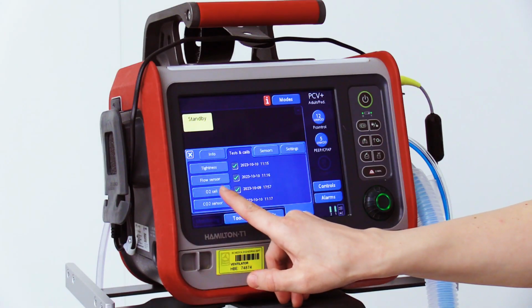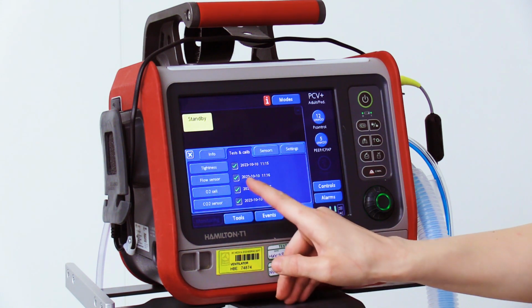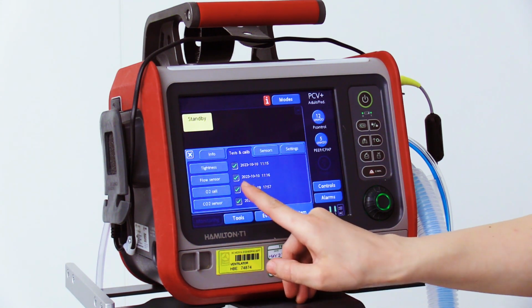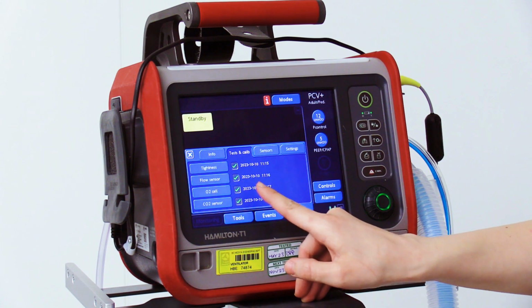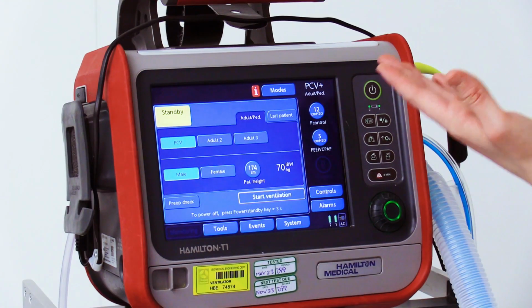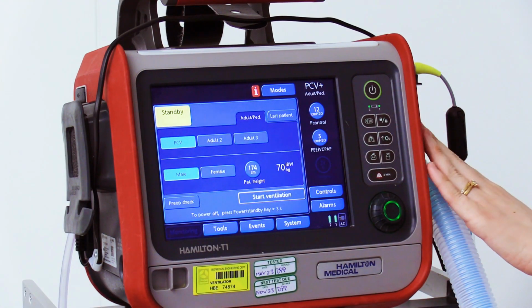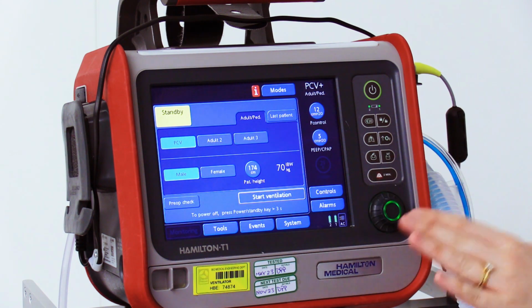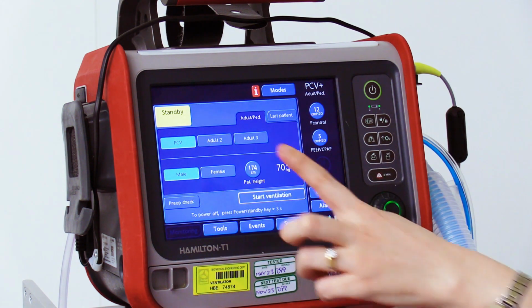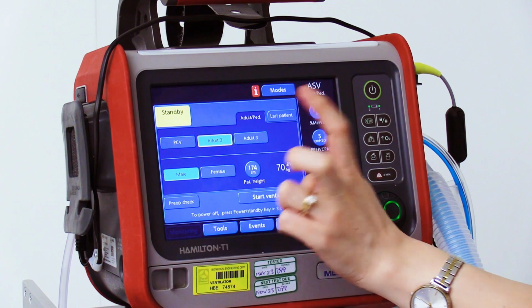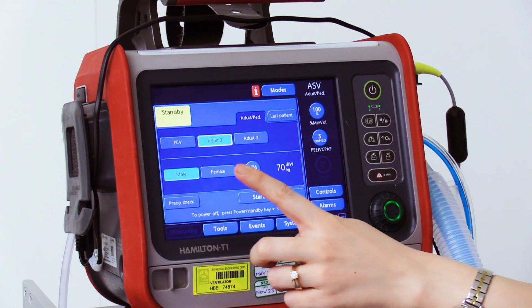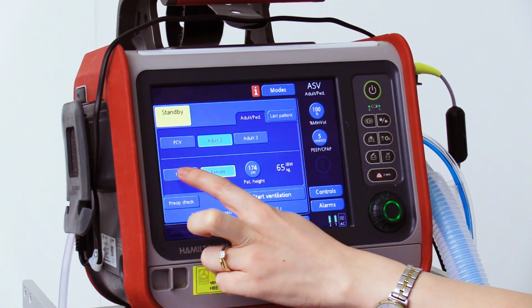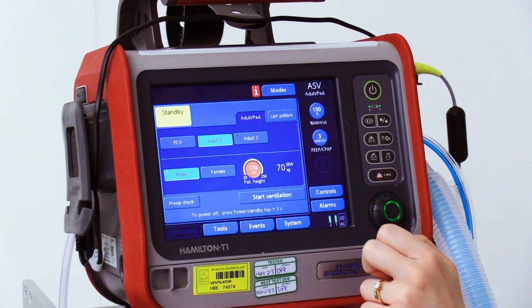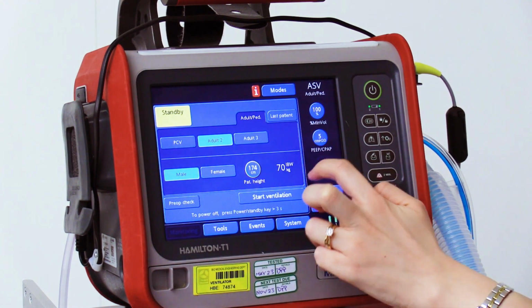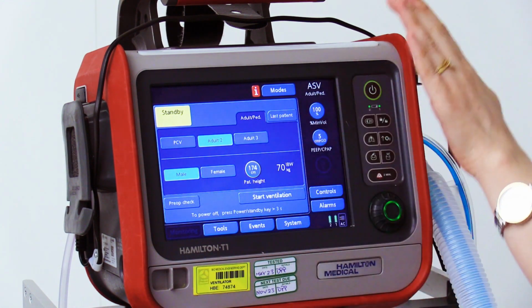You only need to calibrate the O2 sensor if a red X mark is displayed in the O2 sensor. Calibration takes around 2 minutes. Now, the Hamilton T1 ventilator is ready for use. To ventilate your patient, you have to select the right patient group, adult or pediatric. Select male or female, and then you can specify the patient's height. Based on this information, the ideal body weight will be calculated by the T1 ventilator.